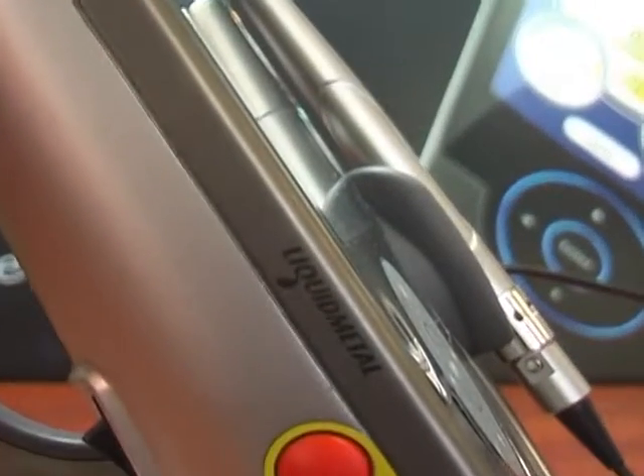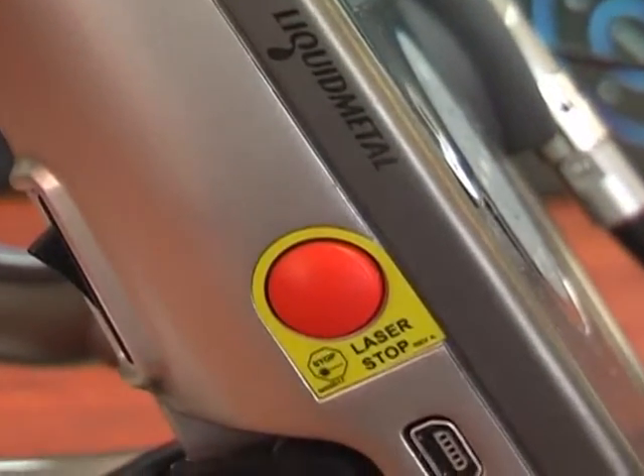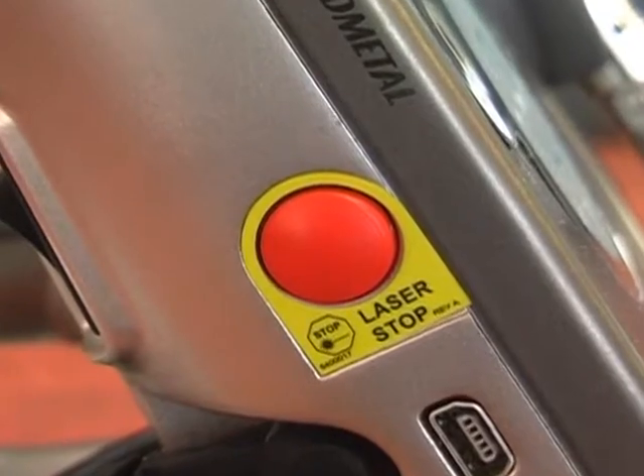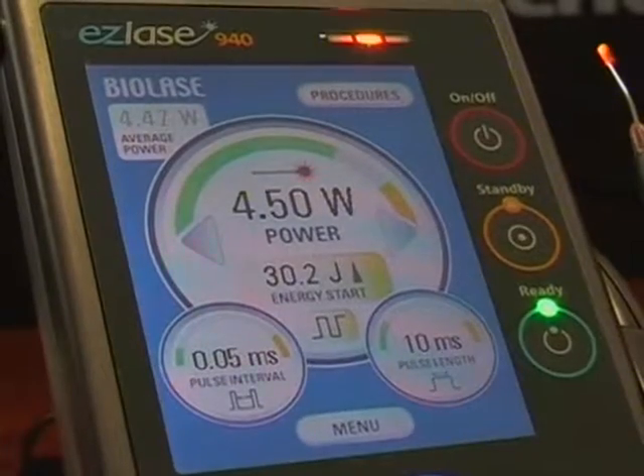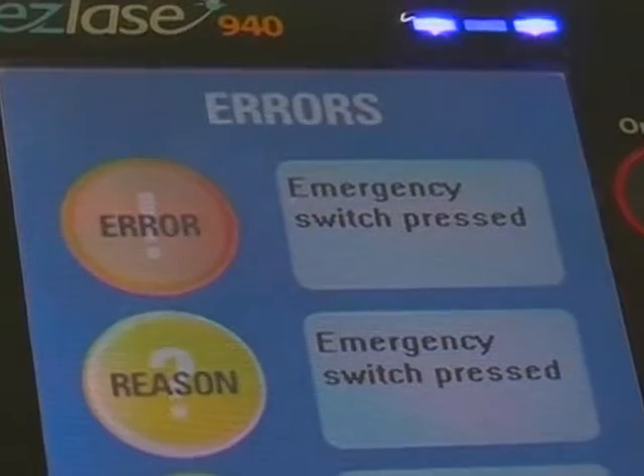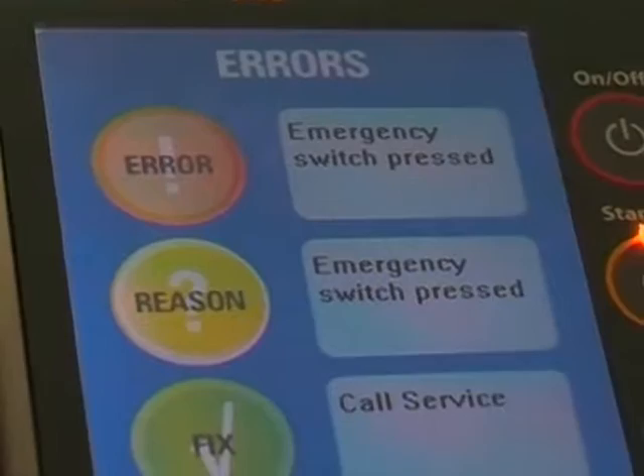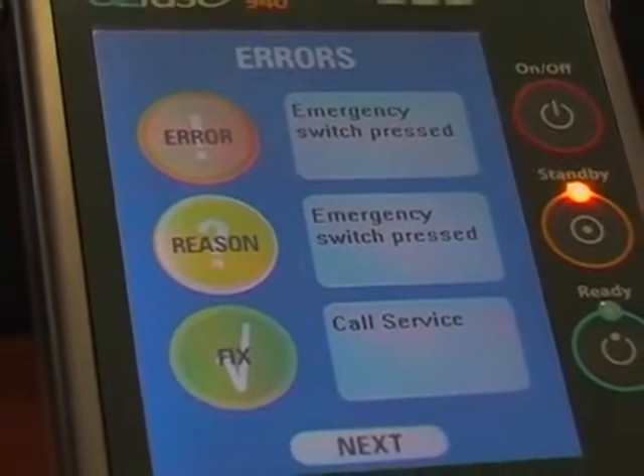There are a number of safety features on the laser. Most important is the emergency stop button in case you need to quickly stop the laser from firing. For instance, if someone without laser safety glasses enters the room in which the laser is operating, all you need to do is hit the red button on the side. It will stop the laser and show this error message. Depress the button again to return to normal mode.